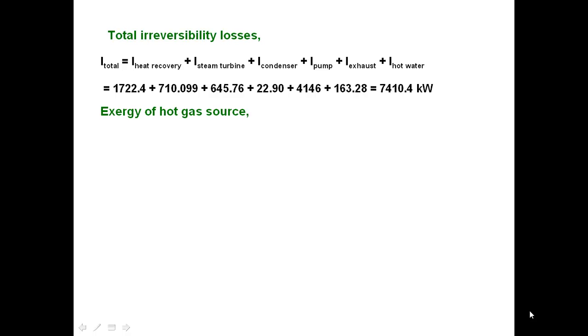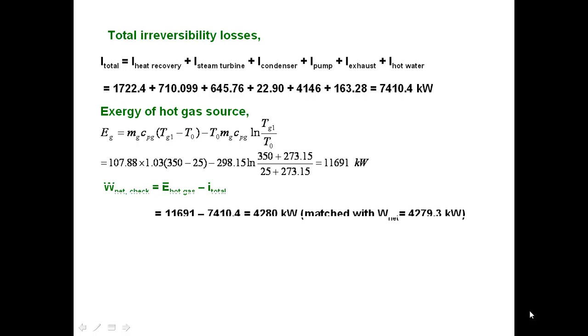To find the second law efficiency, exergy of hot gas is required. From the formula, exergy of hot gas obtained is 11.691 megawatts. Similar to the first law efficiency, that is energy balance, the exergy balance gives the work output from the steam power plant. W net is equal to exergy of the hot gas minus total irreversibility. That is equal to 4.28 megawatts.